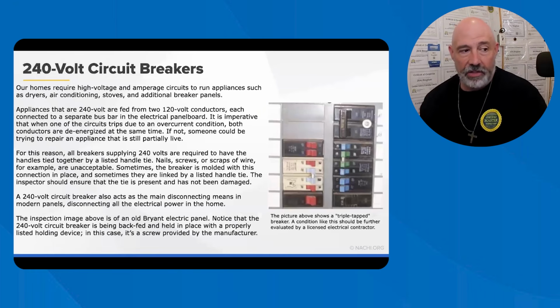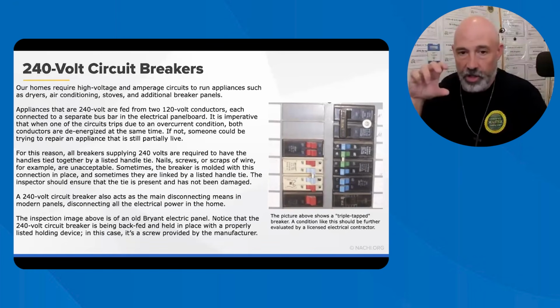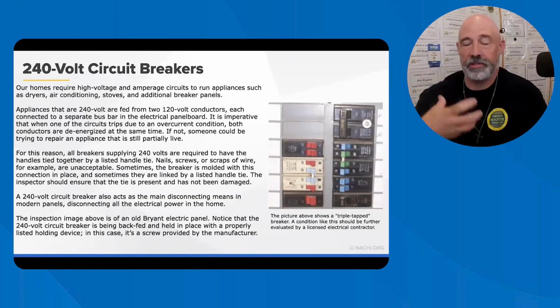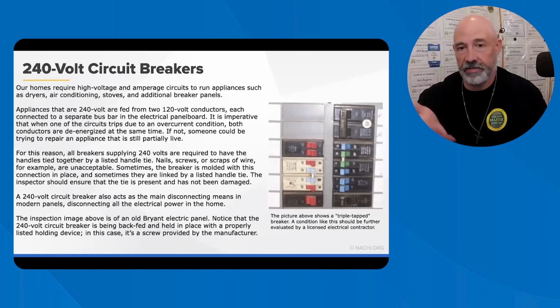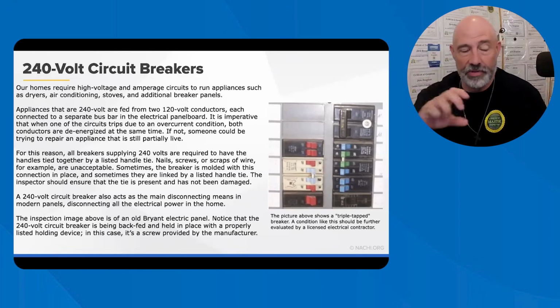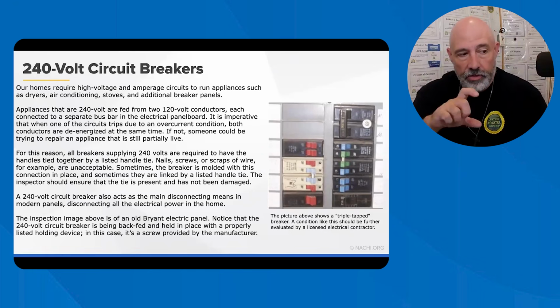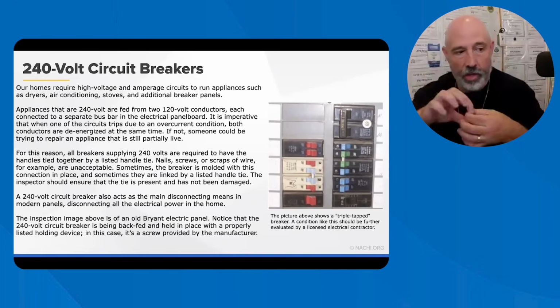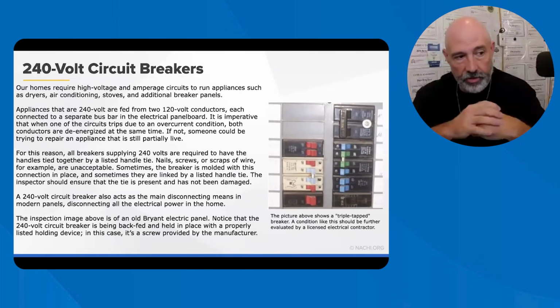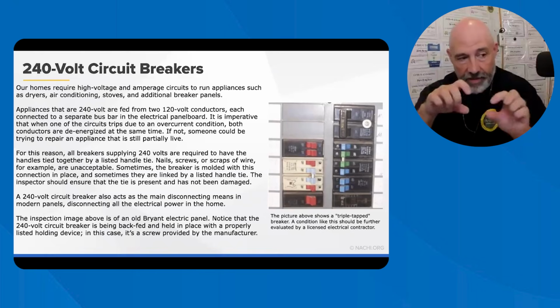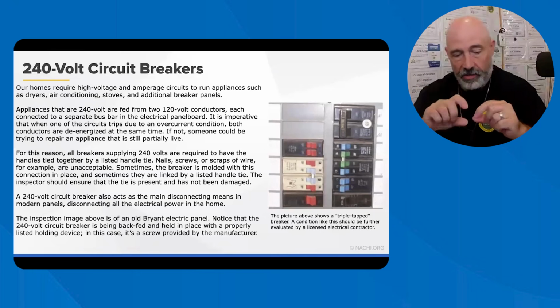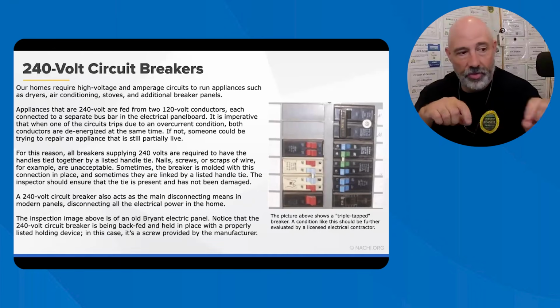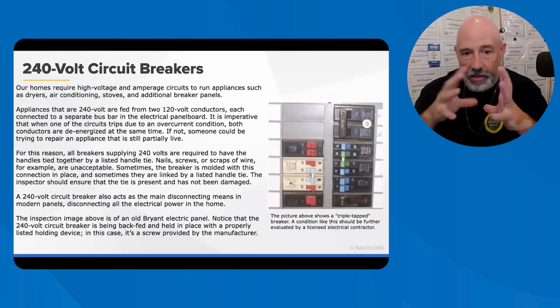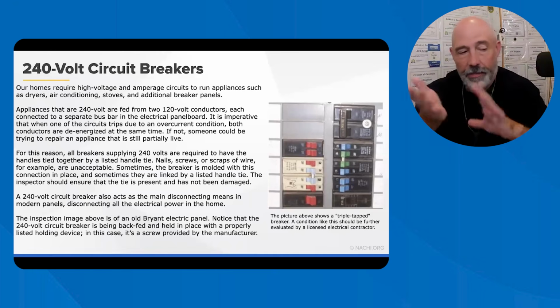Here are some handle ties. If you're looking at the handle ties, they're where two circuit breakers are together, and you must have a handle tie. So if one trips, they both trip. That way one side of the system doesn't come energized while the other side isn't. That's why you want those handle ties on there. Earlier, they used to make handle ties that actually slipped right through the breakers, and you can see that on the green one there. If you look at the circuit breakers, a lot of them still have that hole, so you can still use those, but they have to be compatible with that system.